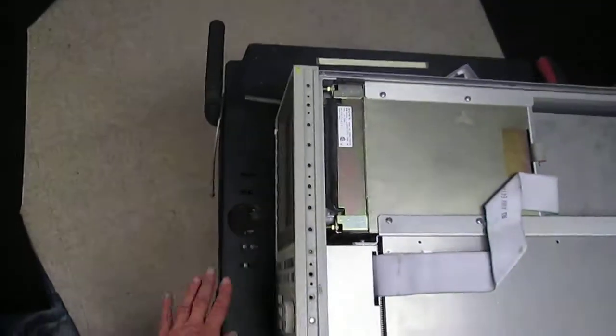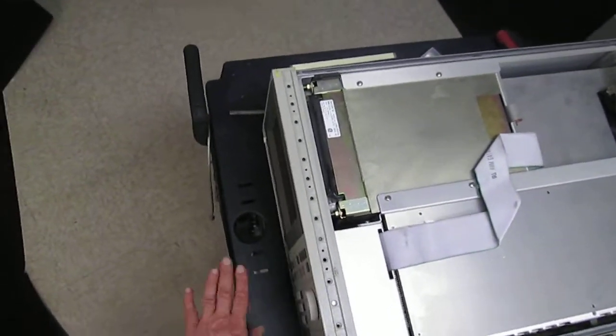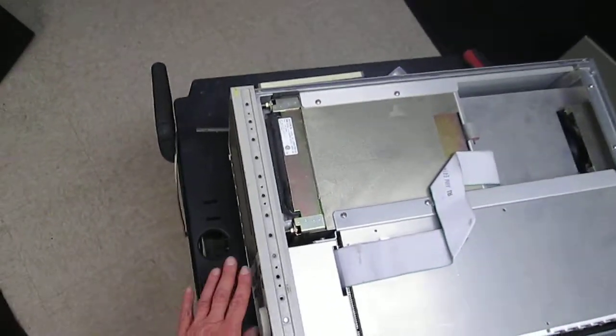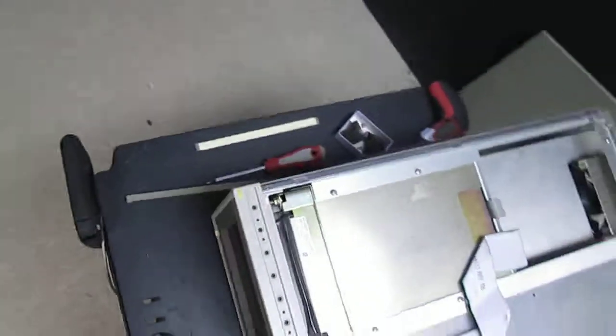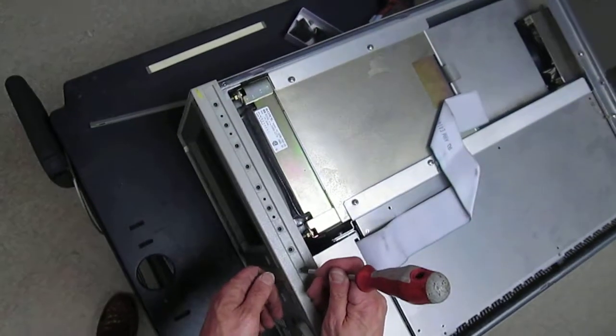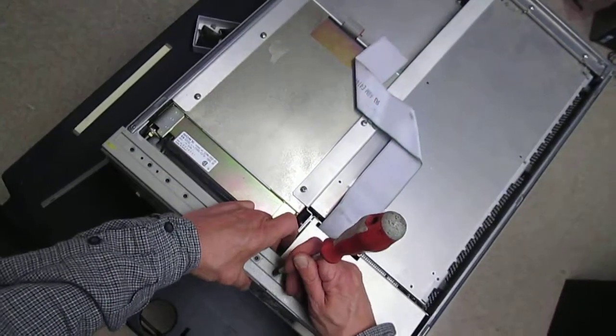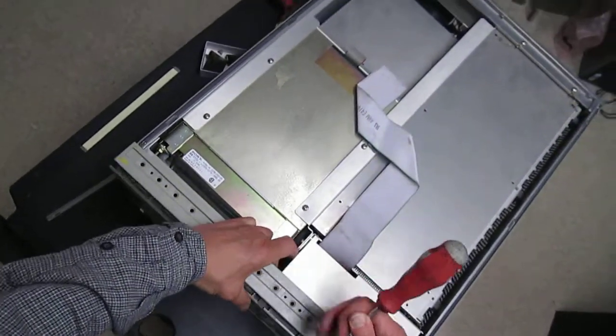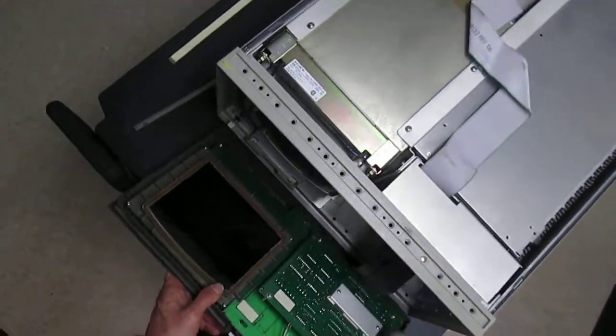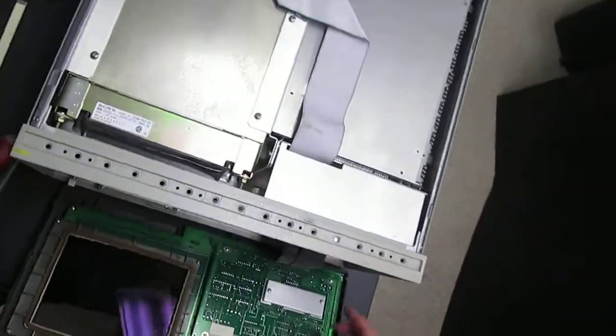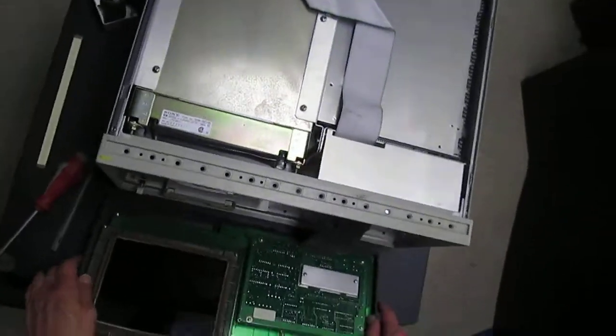Now we're ready to take the front panel off. Again, I use a cart which doesn't have enough space really to hold the front panel. I do not recommend you do it the same way. Find some suitable table or a cart that has more room in the front so you can lay the front panel down safely. Push on the latch and with your finger from the back, push forward. The front panel comes out very easily. Now you lay it flat. You can unplug the front panel, but it's really not necessary.